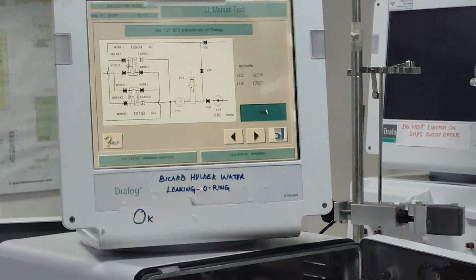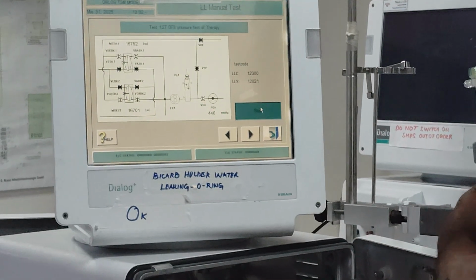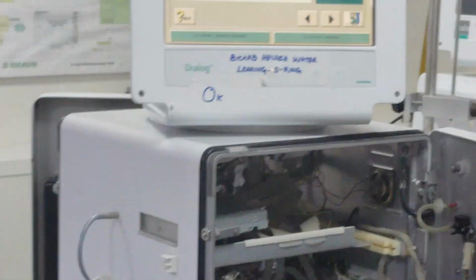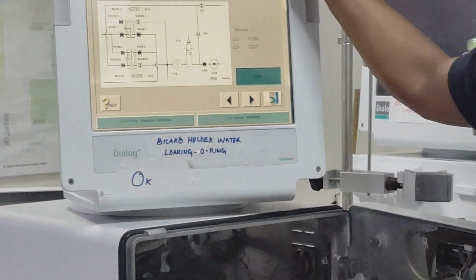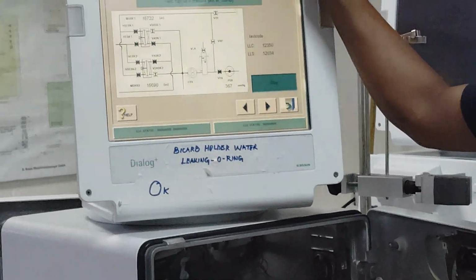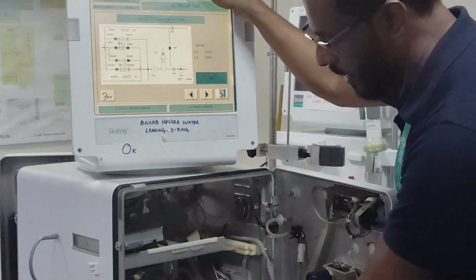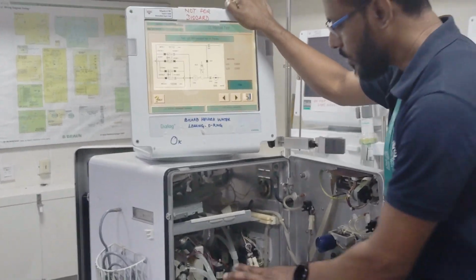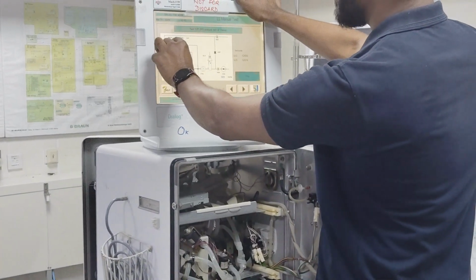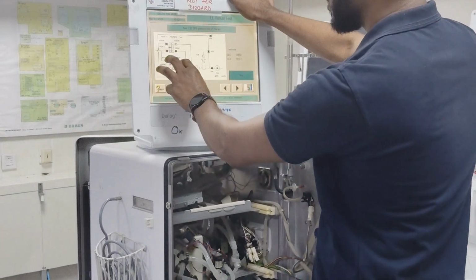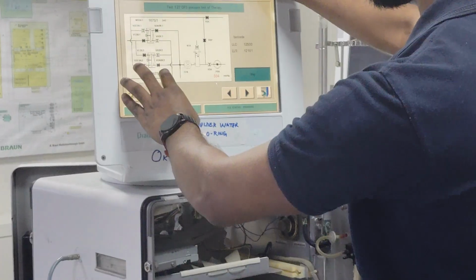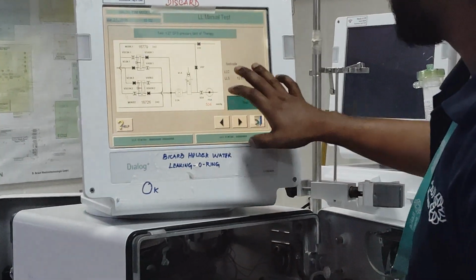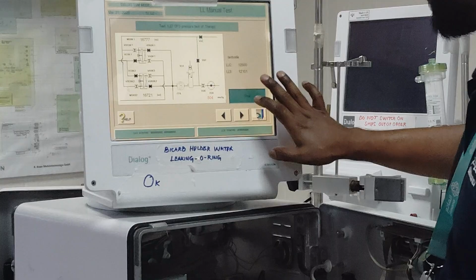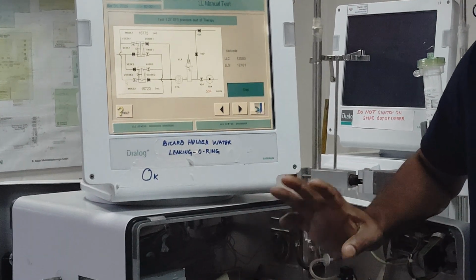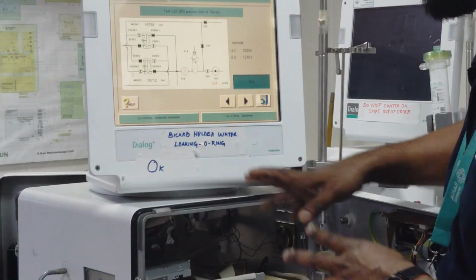What is DFS? Dialysate flow sensor, right? It is the dialysis flow sensing, the pressure connected to the dialysis. So you can see the DFS pressure test, especially after the dialysis therapy. It is trying to check your dialysis pressure, to make sure that all the valves inside are working fine. Each valve is tested, opening and closing. This valve will be open now, and it checks that the valve is open. Then the test will complete, and only then can they proceed to the next dialysis. If the test fails, they do not continue the dialysis. So that is the machine checking all these things.